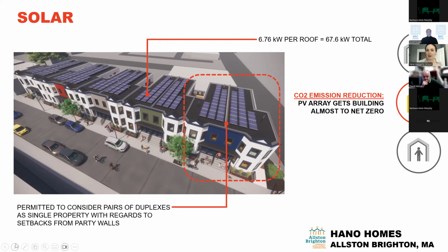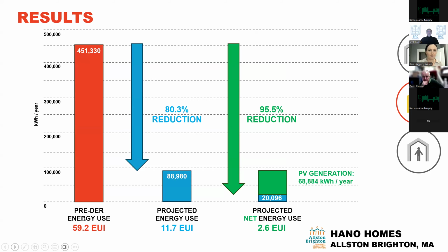That ends up being a 67.6 kilowatt array. We started at a 59.2 EUI, which isn't as awful as we've seen. After just the DER improvements, we can get down to a projected 11.7 EUI, and once we add in the solar, the projected EUI comes down to about 2.6—pretty awesome, and we're happy with that number for sure.